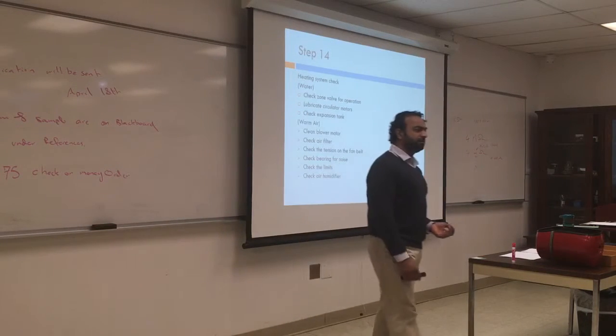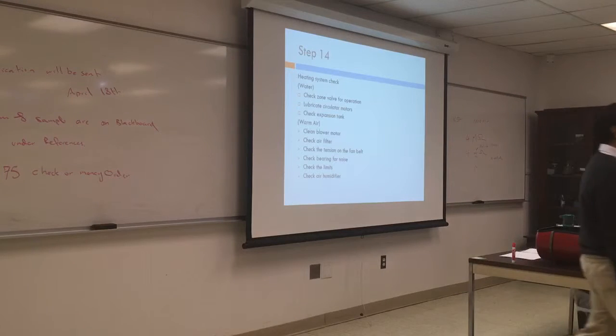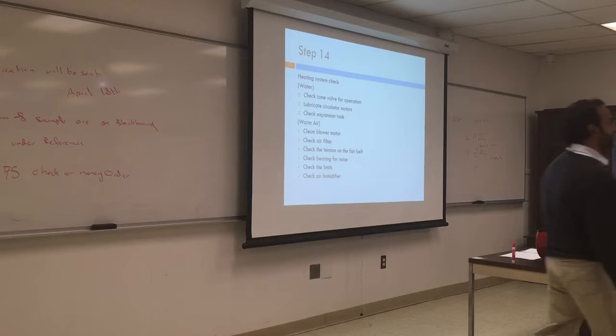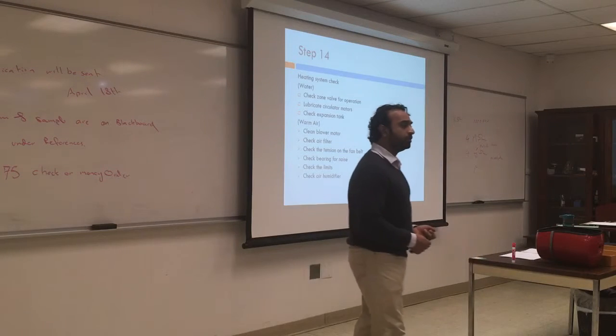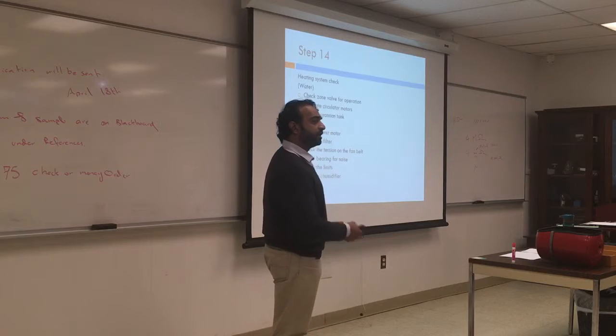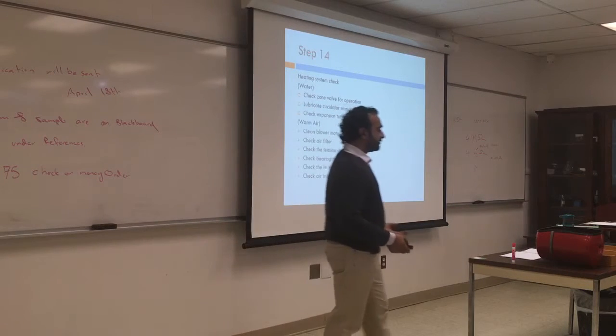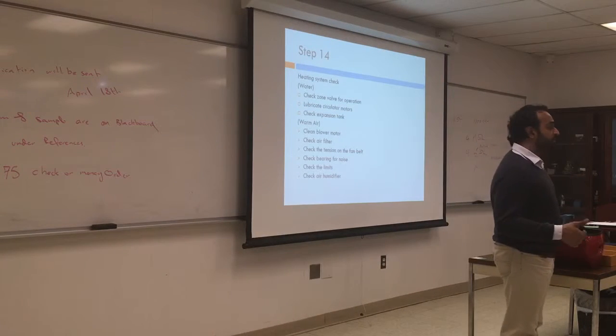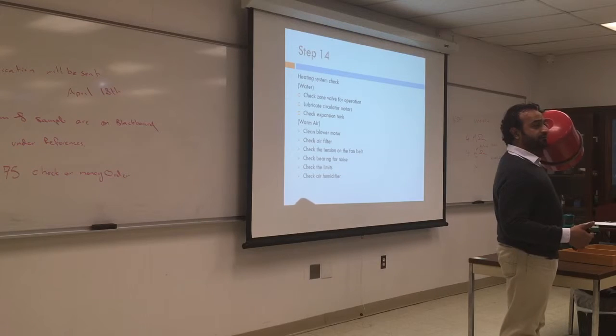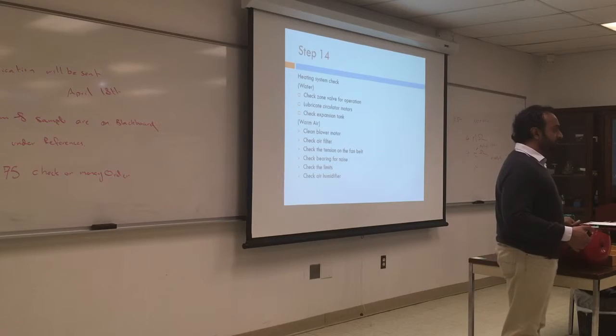So that'll make you think that you need to have a thermometer with you to check the water or the air temperature. So we also want to verify that the air temperature is what it says on the thermometer. Maybe the thermometer needs to be recalibrated. So make sure you have a thermometer with you. You have a complete set of tools so you can check for pressure. Pressure gauges for the pump. Small pressure gauges for air. For gas, check the expansion.